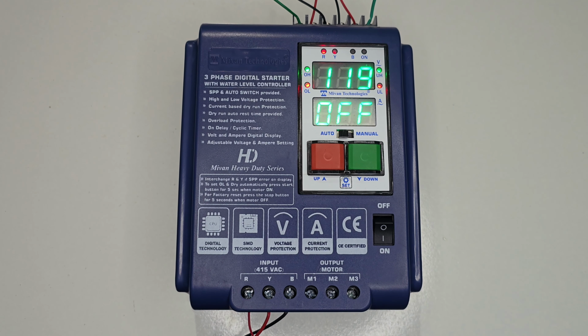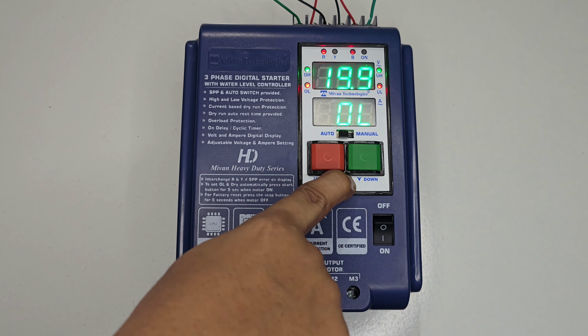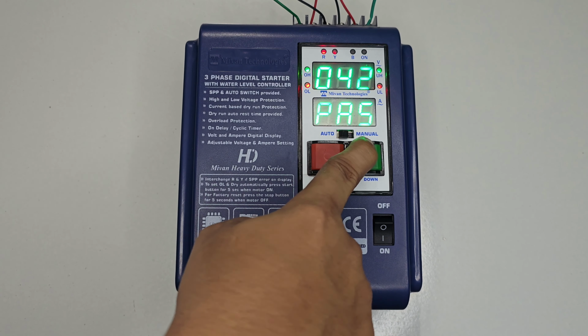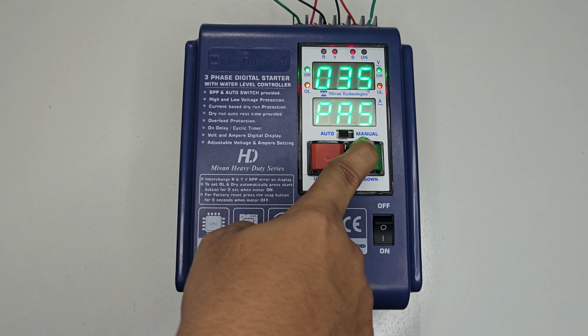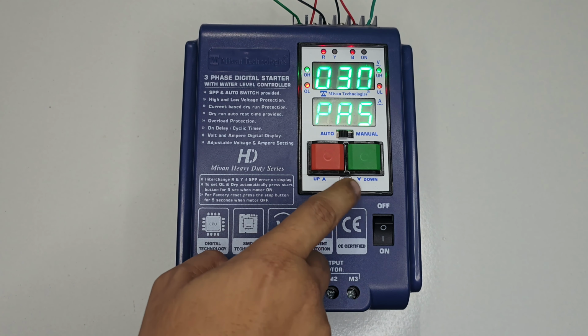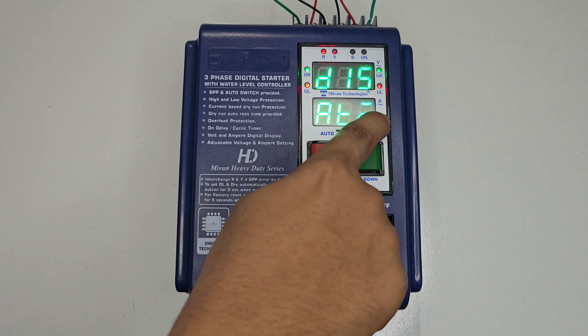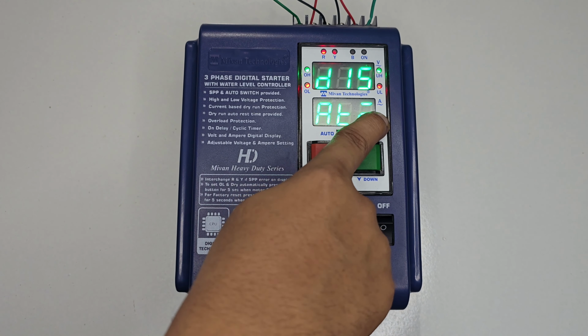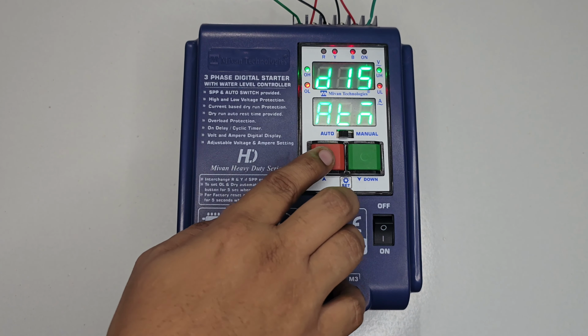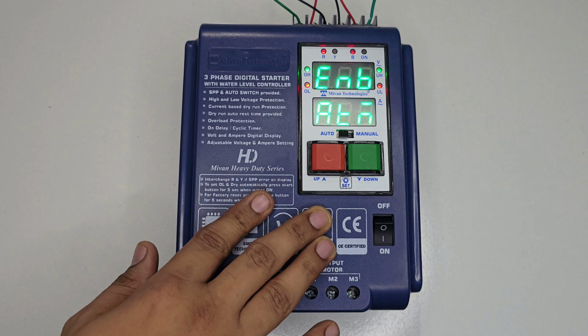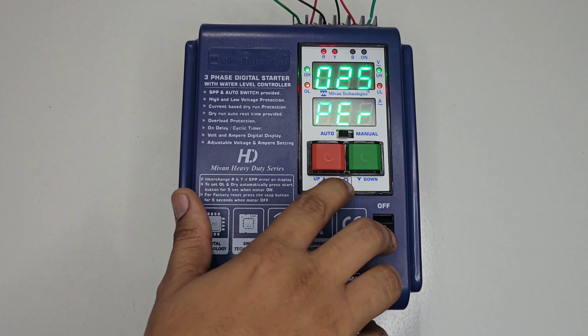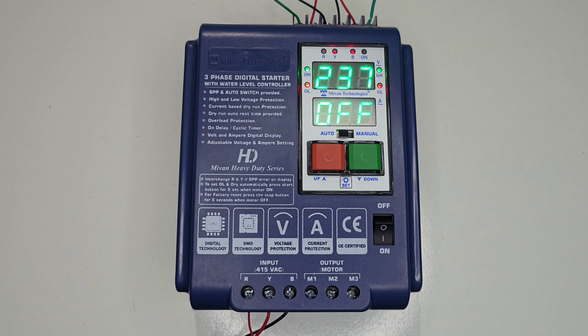Now I'll show you how to set the on delay time. To set the on delay time, press the set button for 5 seconds. Go to password 30. Press the set button. Here you can see ATM, auto timer, auto on timer. Make it enable by the up and down key. Press the set button, and it comes to the main menu.